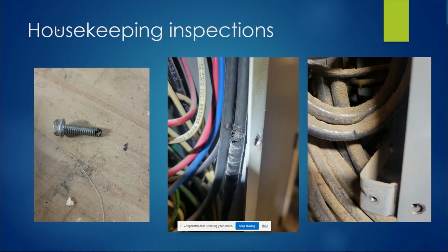Another case in point was where they had so much wire stuffed into the enclosure that they pinched the wires when they put the cover on and cut into the insulation. That's what you see in the picture on the right. So these are all things we identify when we do a housekeeping inspection, along with the rodents and the sawdust and all the other things that we come across. We tend to try and fix those things for you if possible while we've got them open. But if it's something that requires you to shut the piece of equipment off, then we would just put it in our report and give it to you and let you schedule a proper downtime to take it apart and clean the equipment offline.